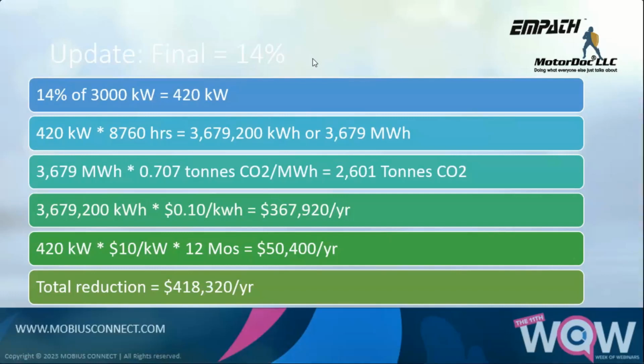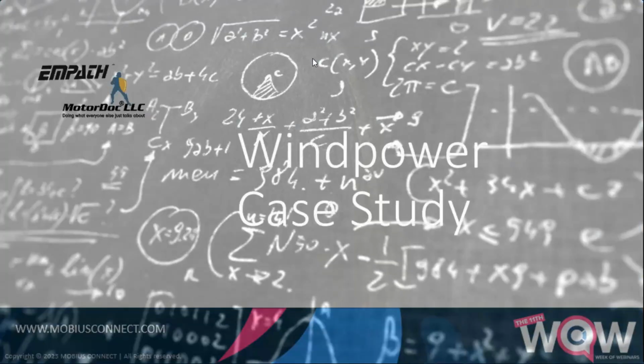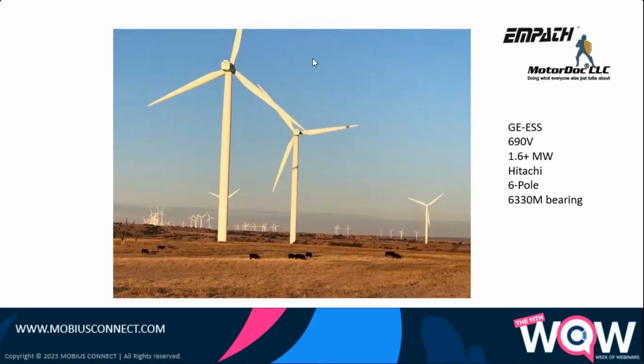So if we take a look at that, and I use the totals I have there, then we take a look at 14% improvement. We take a look at everything else. The total percent reduction in energy for implementing a maintenance program at that facility was guesstimated at $420,000 per year. The end result was much, much higher. So it's always conservative. Now let's take a quick look, because I mentioned bearings, and then we should have time for questions. I'll go really fast because I've used this case study before.